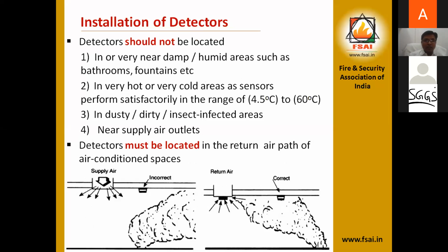So, in very damp or humid areas, such as bathrooms and fountains, we should avoid placing the detectors. In very hot or very cold areas too, as sensors perform satisfactorily in the range of 4.5 degrees Celsius to 60 degrees Celsius. In dusty, dirty, insect-infested areas near a supply air outlet, we should avoid installing the detectors. You can see in this figure the supply of air, and the detector is installed immediately near the supply of air. This is the incorrect position.